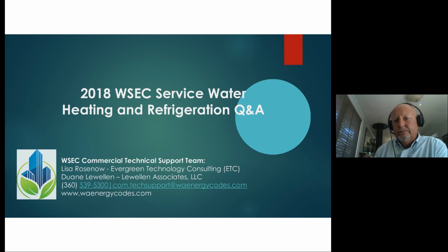Okay, that's helpful. So Derek has another question. If we replace an electric tank type water heater that fails with age, do we have to bring the entire hot water system fully up to code? That's a good question. I would say no. It's not the intent of the code for existing buildings to require full compliance. Now, the new water heater has to meet the code minimum requirements for energy factor, but the entire system, if it's over 1 million BTU an hour or whatever, doesn't have to meet the full requirements of the code.